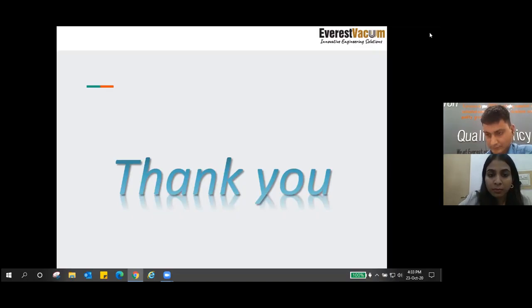Have you designed any booster pump working at low pH, between 3 to 4? Yes, many of our boosters are working in these conditions. If people have covered the last webinar, wherein we covered the super Roots and the super screws, we have our CX models specially designed for these highly corrosive applications, wherein the boosters as well as the primary pumps, the dry screw vacuum pumps, are either nickel PEEK coated or electroless nickel plated. The same goes for the boosters. So we can provide them with PEEK or electroless nickel plating as per the process requirement.